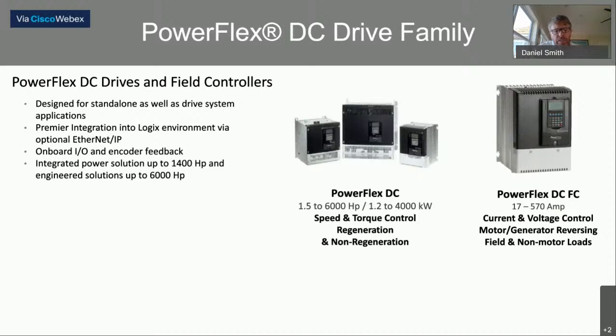The I/O: it has onboard I/O for discrete inputs and outputs. There's already a built-in encoder input embedded in the drive. We're able to add control comms cards to the drive to talk to it. The drive can talk with ControlLogix or CompactLogix over Ethernet. And it's also a drive that can be used on a network or in standalone applications.